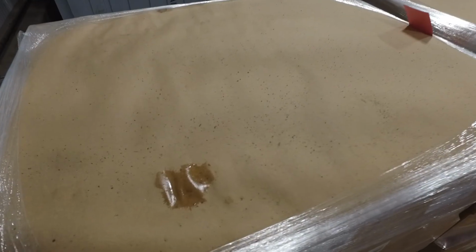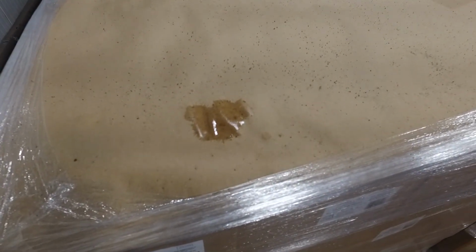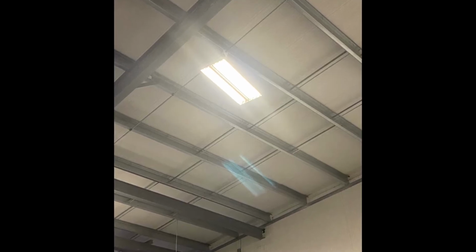These are the most common deficiencies found on cooler ceilings, walls, and floors. Ceilings and walls in the egg cooler are often prone to condensation, especially near panel seams. This condensation can promote mold and mildew growth and become a major product contamination concern. The ceiling can be easily overlooked depending on the height of the egg cooler, but it is important to assess all surfaces for unsanitary conditions.